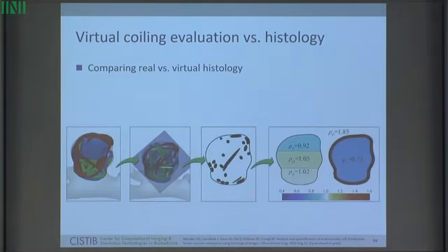Now, how do you validate that? Again, what we found is that the way to validate is to link back the real and the virtual world. So in this case, we can create multiple implantations in different configurations. We can then do a cross-section of this aneurysm, look at the strut intersection with that plane, and then, for instance, define a core area and a shell around, and then different depths with respect to the neck, and look at the density of the coils as they were distributed there.